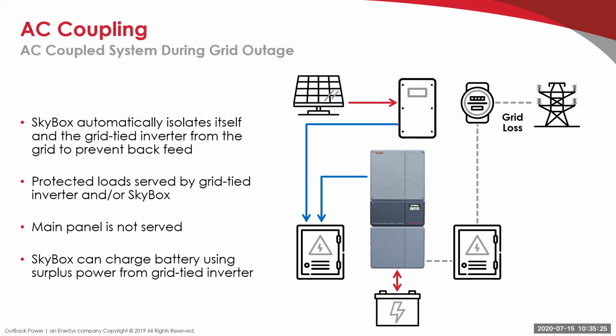I mean, we make sure the voltage doesn't go too high. We make sure the current doesn't go too high, but still it can fall down, and it's just unregulated. The voltage and current can both be highly variable, which is not the optimum way to charge a battery. So if you're just going to have emergency backup power to get you through a week or two of the public safety power shutdown in California or hurricane or wherever it is that you live, that you have some grid outages periodically, that's really what this is intended for.